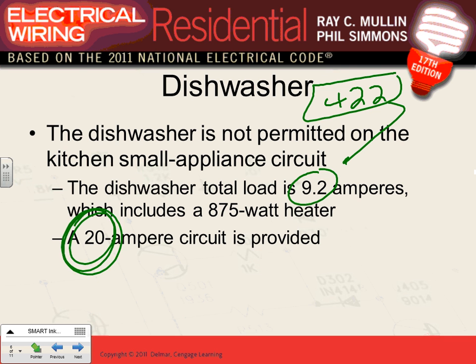20 amp circuit for it. So that's where the 20 amp circuit came to be. 20 amp circuit, and you can apply the same rule also for the garbage disposal. 13 amps or less for an appliance, from Article 422, you have to provide a 20 amp circuit. Otherwise, you start multiplying by 1.5 for the overcurrent device. Okay, so that's basically why we came up with the same thing.